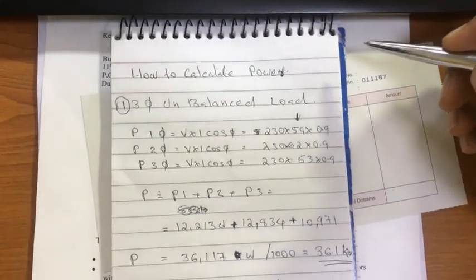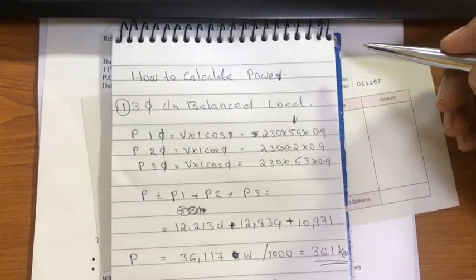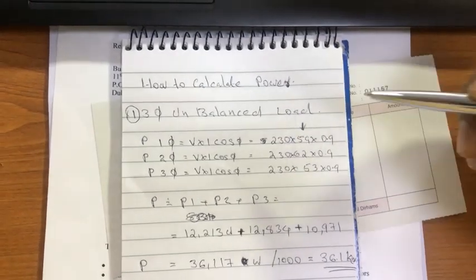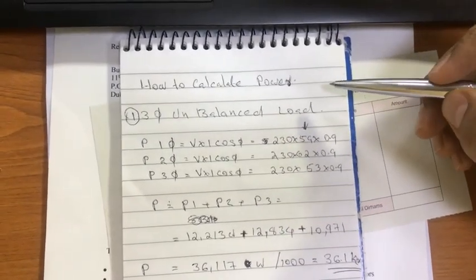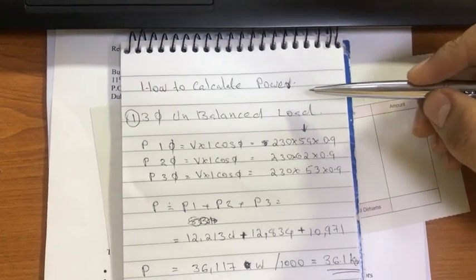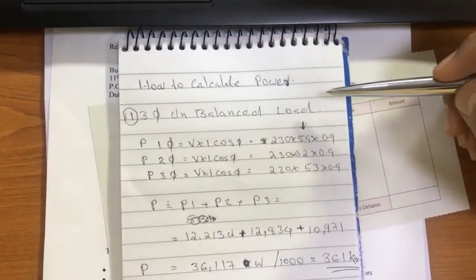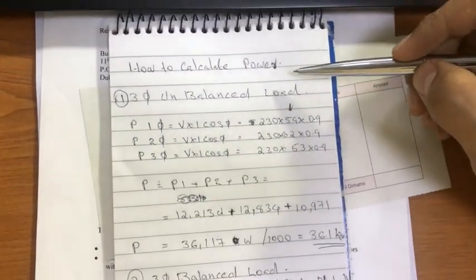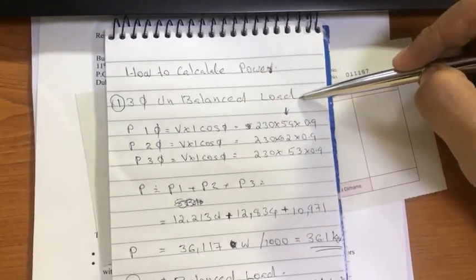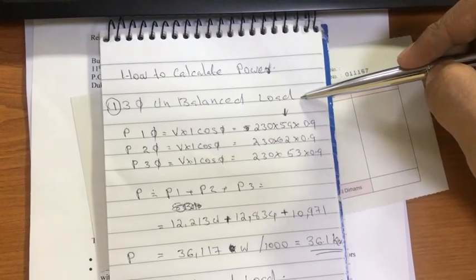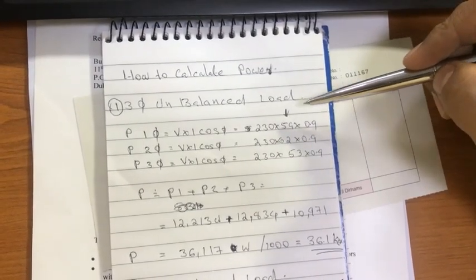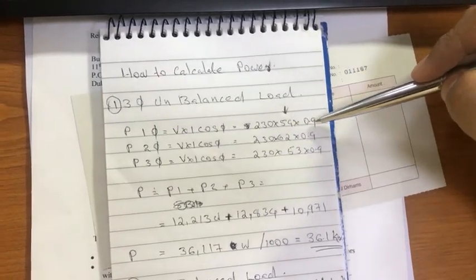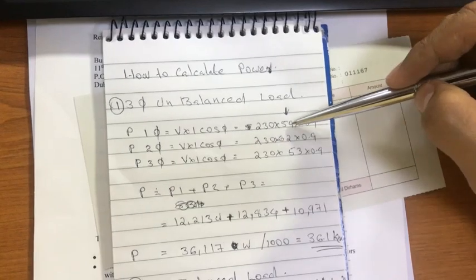In the video we discussed how to calculate the power by measuring the current from the power cable. Okay, here I need to explain some more things. When we have to calculate the power in three phase, there are different methods that we can follow. Like one method, if we have unbalanced load, three phase power with unbalanced load, how do we calculate? We have to measure the voltage in each line, and we have to measure the current in each line.